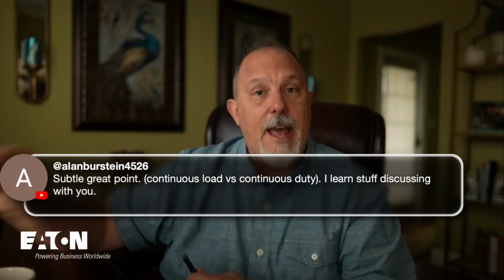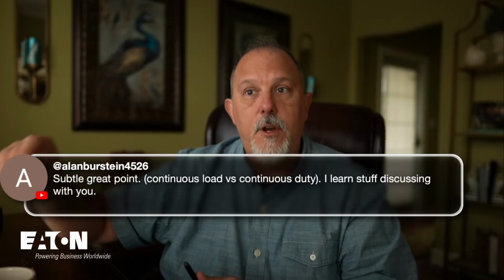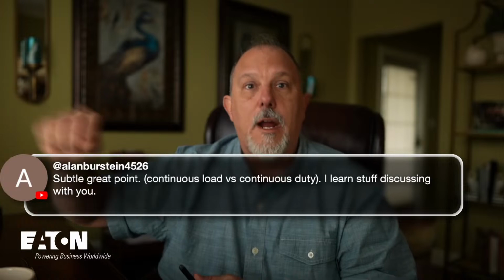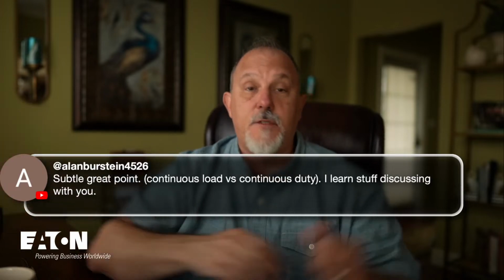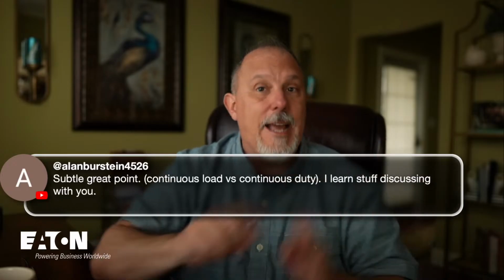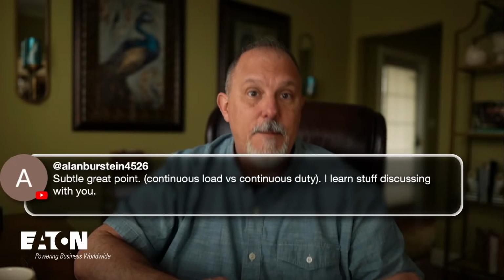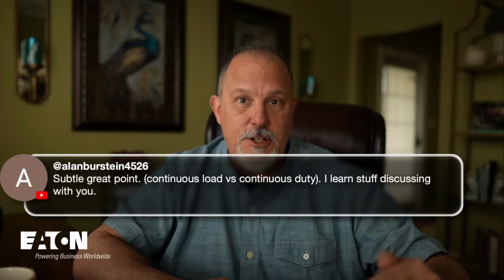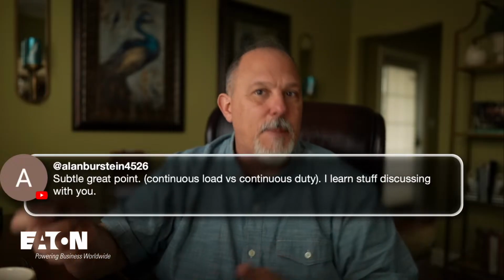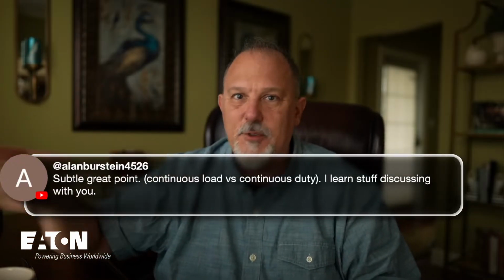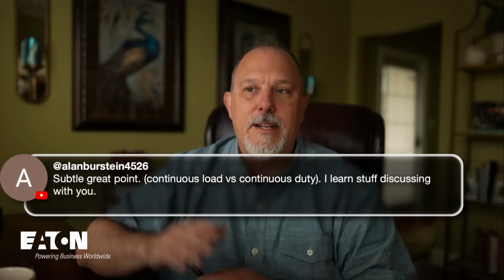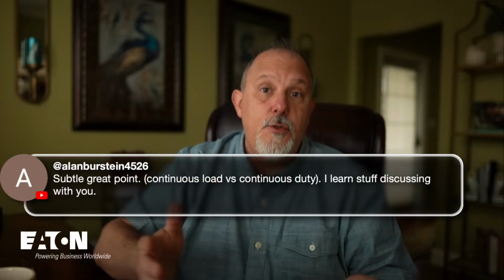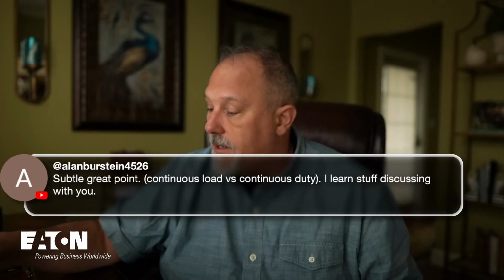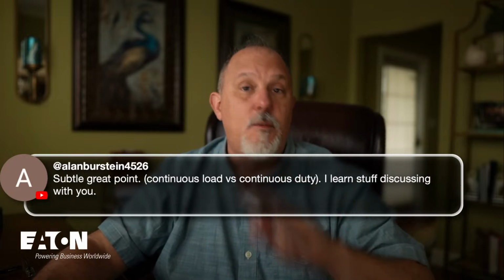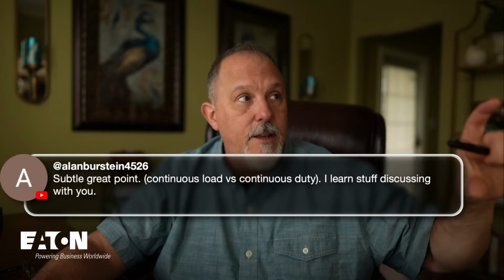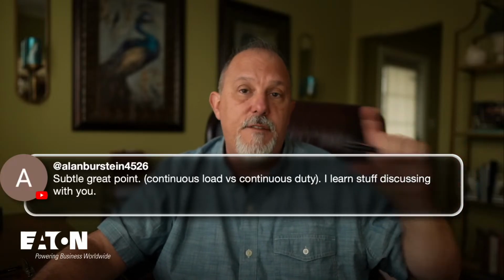I think understanding that will help us understand how to identify an application. Because if you look in 430, it says a continuous duty application, not a continuous duty motor. It says continuous duty application when determining the multiplying factors, whether or not you do the 125%, based on the application, not the motor. I can use a continuous duty motor in a non-continuous duty application. So I'm doing homework on that, trying to learn why these three terms are so vaguely written.